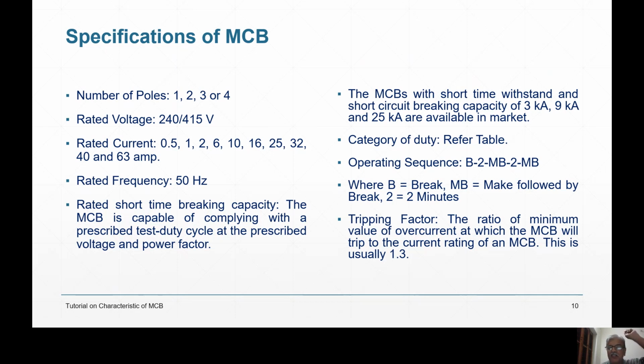And when they passed 6000 ampere, then there was an arc. That arc flew some 2 meters up. The arc was flying 2 meters up the MCB. So we were worried whether the MCB will pass or not. By God's grace, the MCB passed the complete breaking test. And when it passed, we enjoyed. At night we enjoyed a good dinner. We had a party. And when we reached the factory, people also gave us a party because the MCB had cleared the test. The government laboratory has given the certificate. So now we can sell in the market, right?